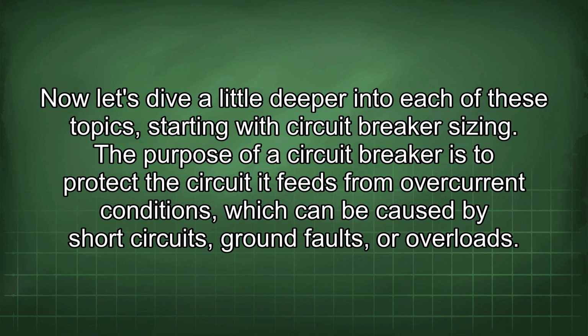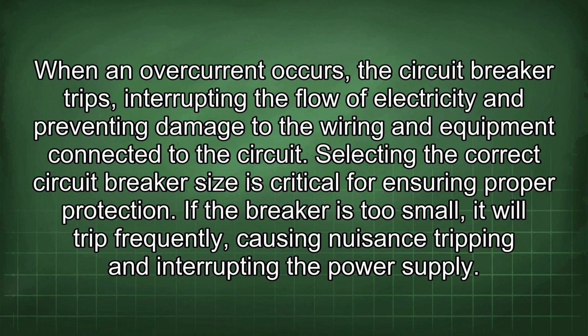The purpose of a circuit breaker is to protect the circuit it feeds from overcurrent conditions, which can be caused by short circuits, ground faults, or overloads. When an overcurrent occurs, the circuit breaker trips, interrupting the flow of electricity and preventing damage to the wiring and equipment connected to the circuit. Selecting the correct circuit breaker size is critical for ensuring proper protection.